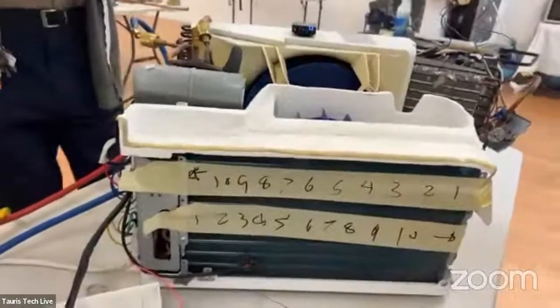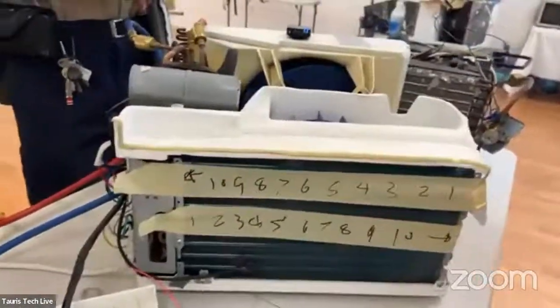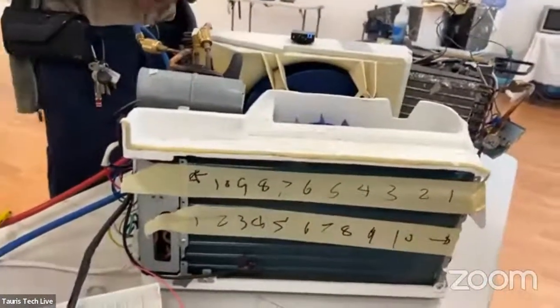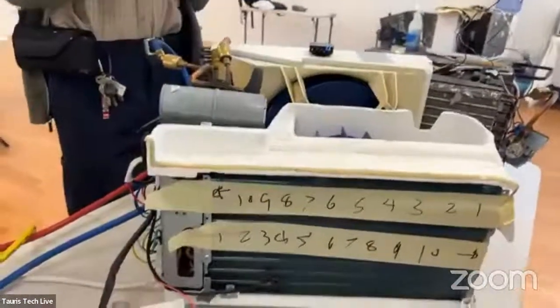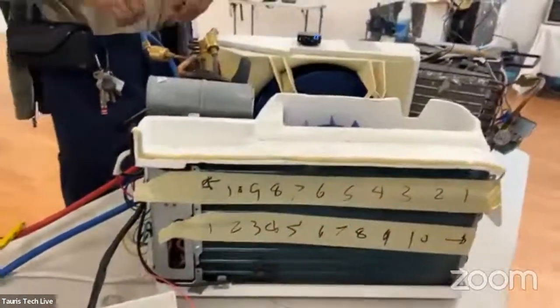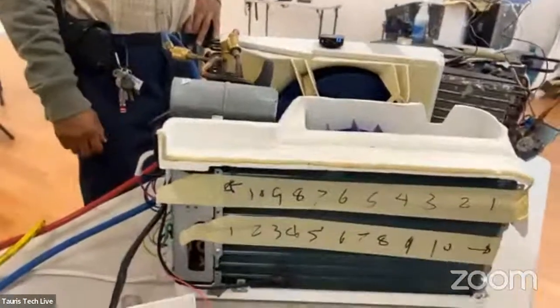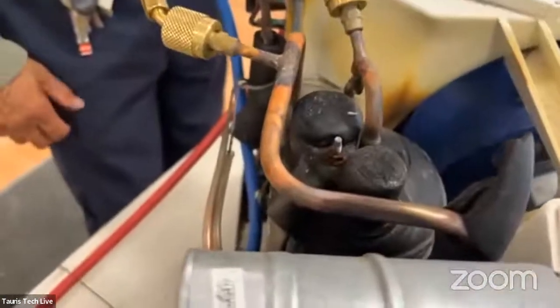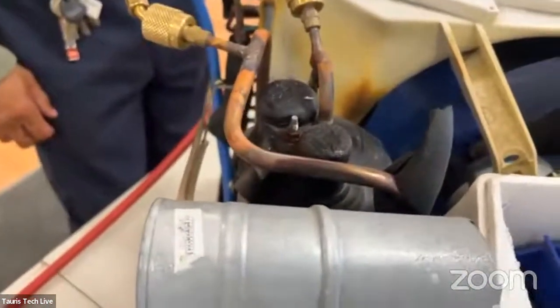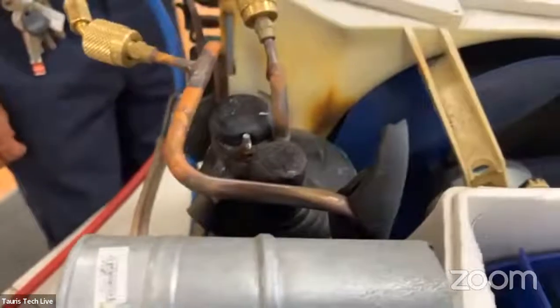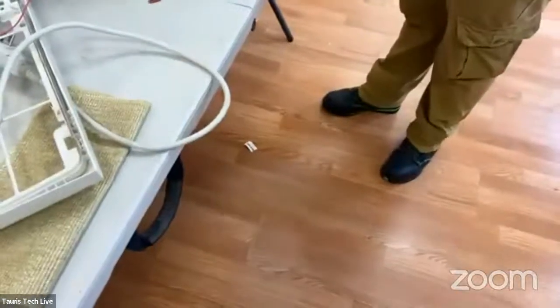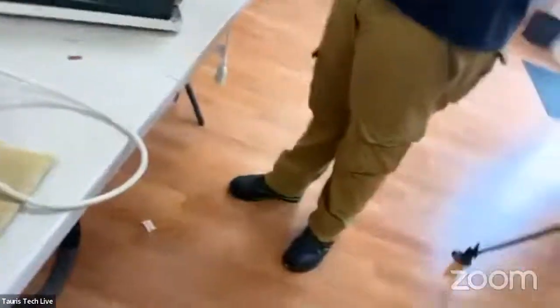And I'm not just talking about air conditioners. We're going to see bigger and bigger machines. You have to understand all these things. You have to know what the words mean. So if I say to you, what is my superheat? And you say, oh, I got 50 degrees of superheat. Guess what? The compressor is going to die very soon because you're not properly cooling off the compressor motor. So all of this stuff is tied together: the right voltage, the right temperature, and the right pressure.